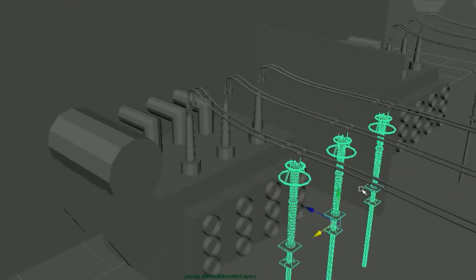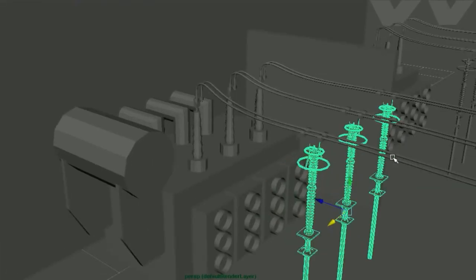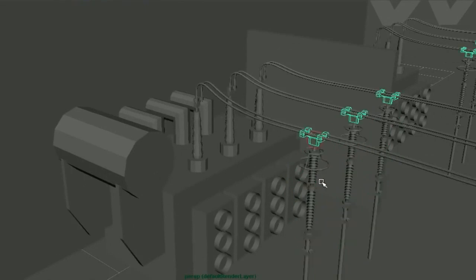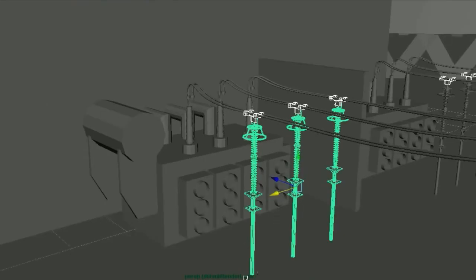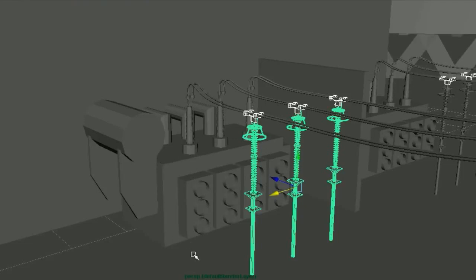Transformers are equipped with surge arresters that ground any voltage surge coming from the system to the transformer and prevent it from entering the transformer. They are connected in parallel — one terminal is connected to the line conductor and the other is grounded. As soon as voltage increases beyond a limit — for example, on a 400 kV line if voltage suddenly rises 3–4 times — the extra voltage is earthed by the surge arresters. In many models, surge arresters are mounted directly on the transformer tank since the tank is also connected to earth.